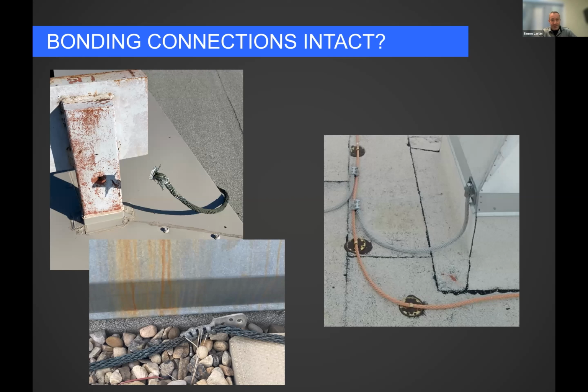There's some non-intact bonding connections. Roofer special in the top left. That I think is just wear and tear and maintenance that somebody wasn't paying attention on. The bottom, that's a Calgary high rise. I think they replaced some rooftop equipment and then never replaced the bonding connection. So that's a thing that does happen a lot in maintenance. Whereas on the right-hand side, of course, there we have the bonding connections. They're nice and solid. And that's no problem at all there.